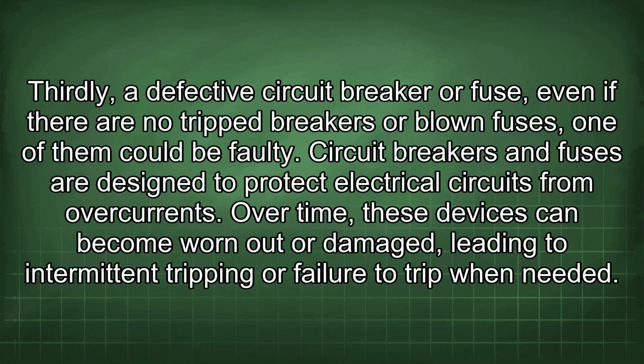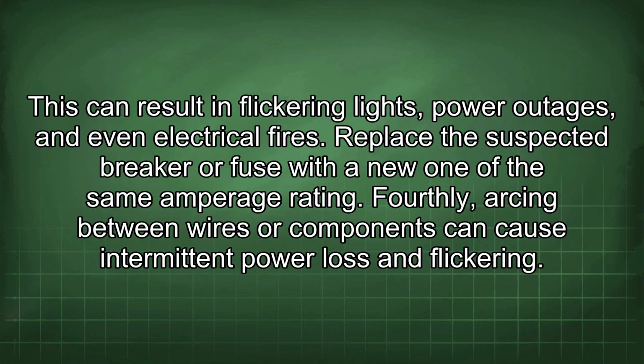Thirdly, a defective circuit breaker or fuse. Even if there are no tripped breakers or blown fuses, one of them could be faulty. Circuit breakers and fuses are designed to protect electrical circuits from overcurrents. Over time, these devices can become worn out or damaged, leading to intermittent tripping or failure to trip when needed. This can result in flickering lights, power outages, and even electrical fires. Replace the suspected breaker or fuse with a new one of the same amperage rating.